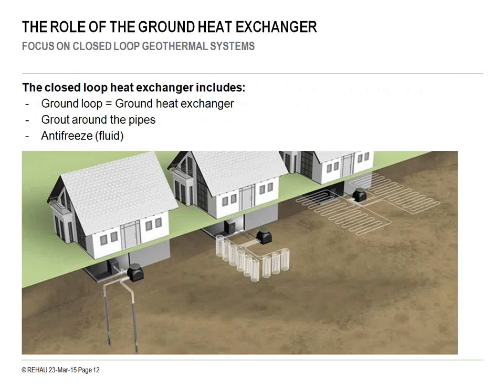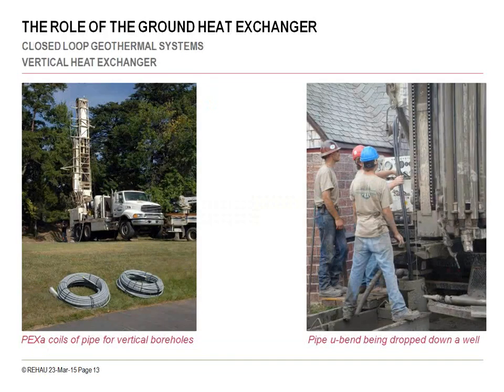The closed loop heat exchanger includes the loop itself. There's a grout that is used from the bottom of the boreholes all the way up to the top, and then often there would be an antifreeze solution, water treatment solution as well in a closed loop system. This is showing some of the piping systems there on the left. Those are 2 coils of PEX-A pipes getting ready to be installed for vertical applications. On the right, we're seeing an HDPE U-bend that's being dropped down a borehole.